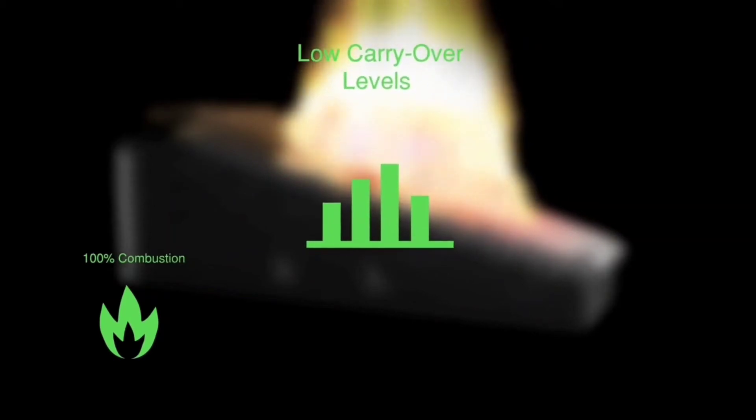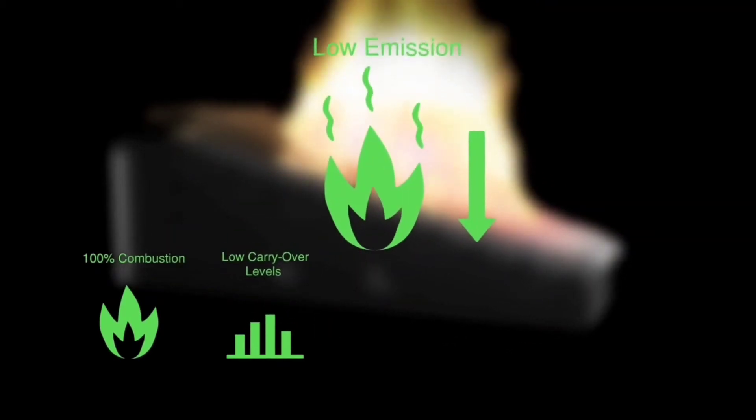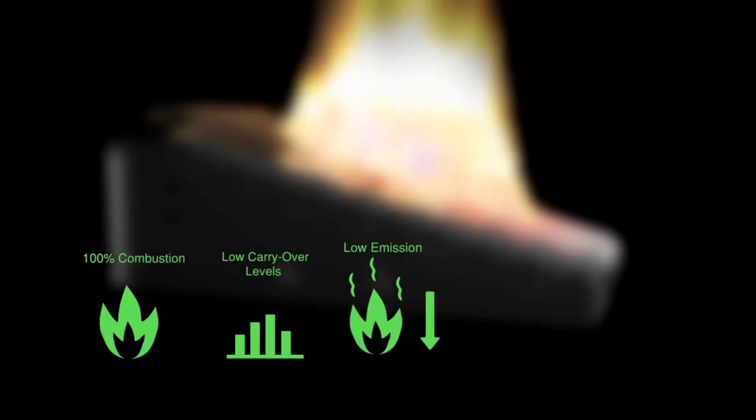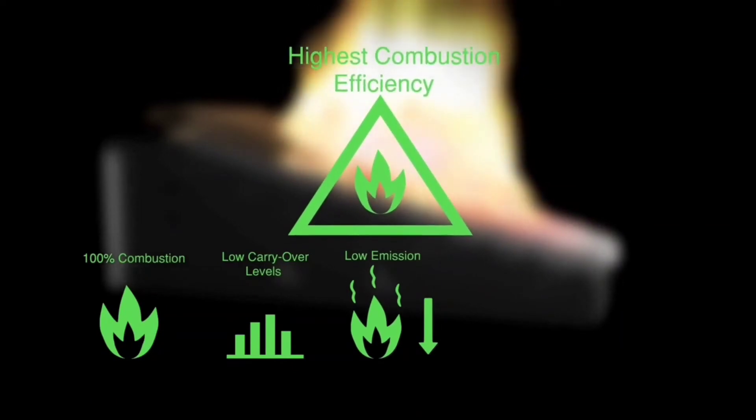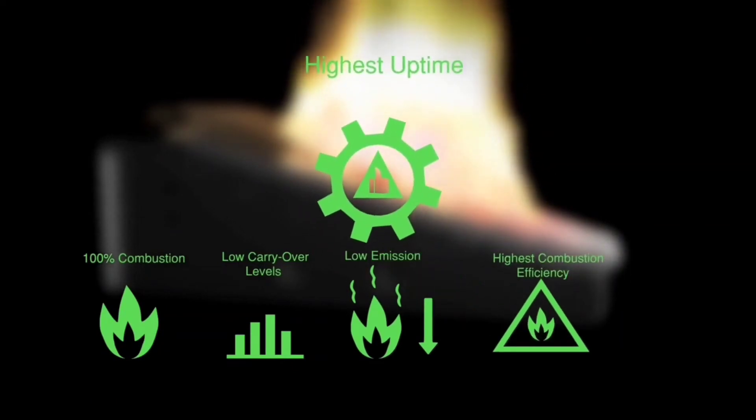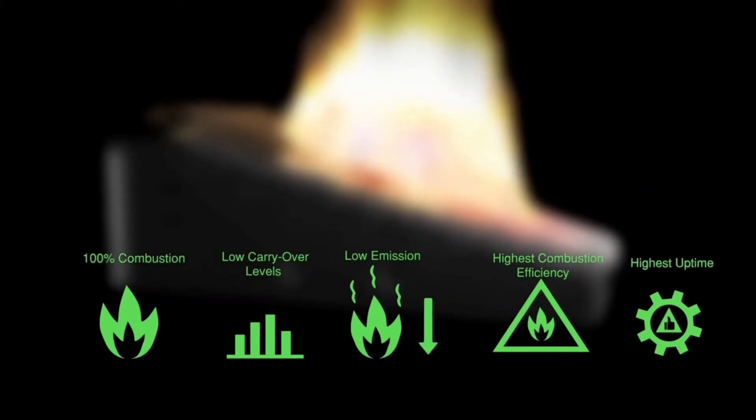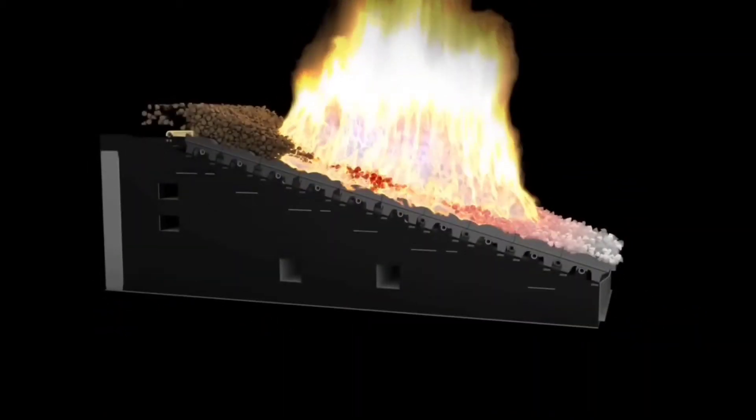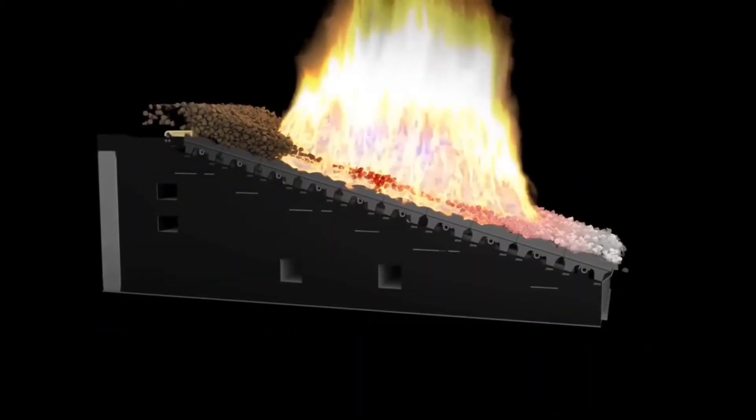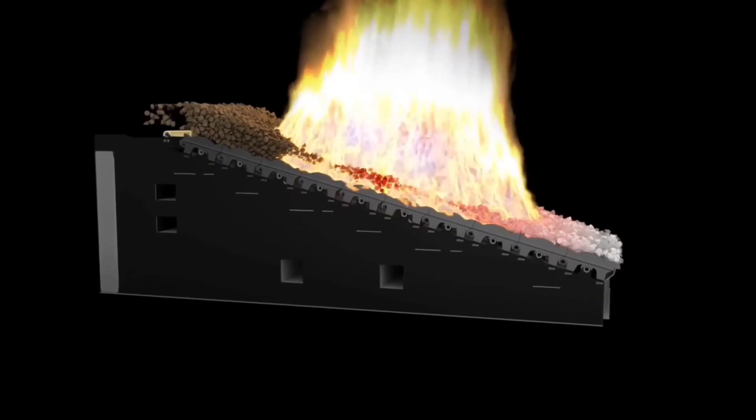The advantages of reciprocating grate are 100% combustion, low carryover levels, low emission levels, highest combustion efficiency, and highest uptime. Relative motion between fuel bed and grate helps deal with poor fuels up to 60% moisture content.